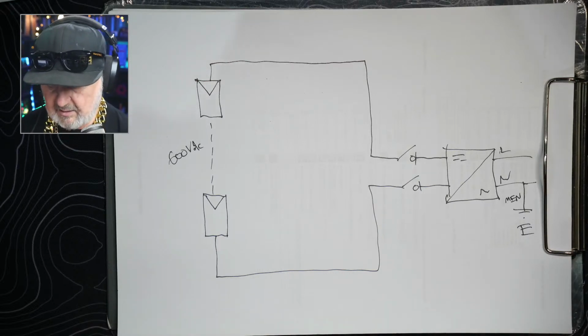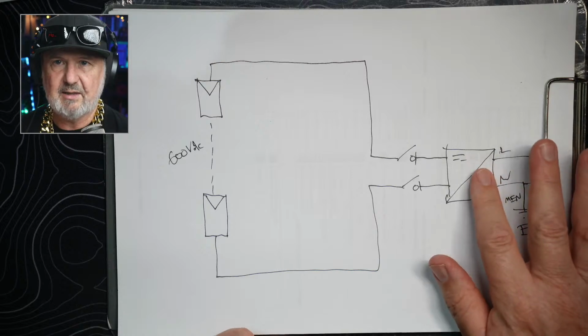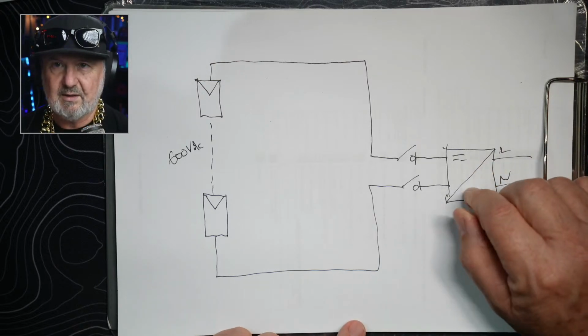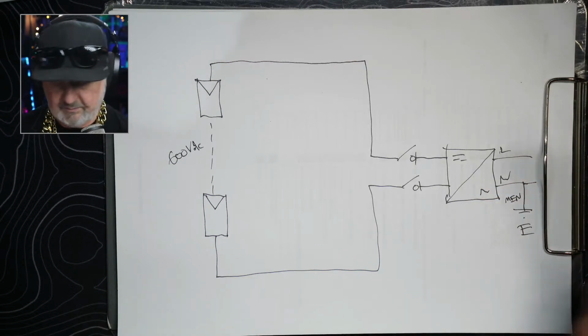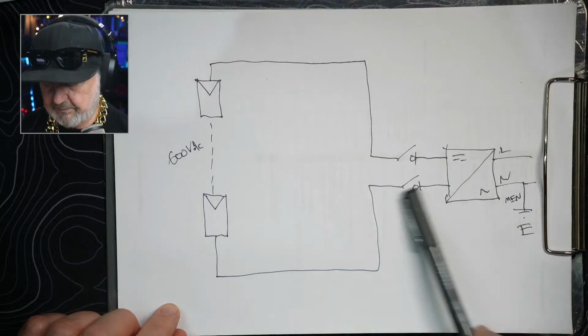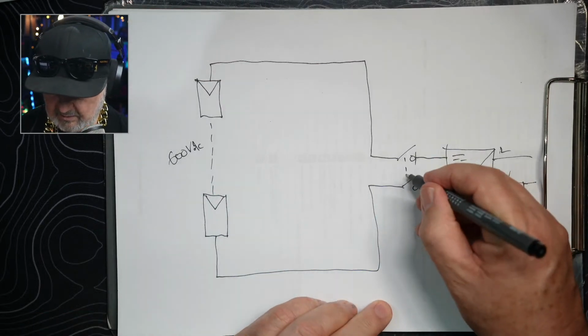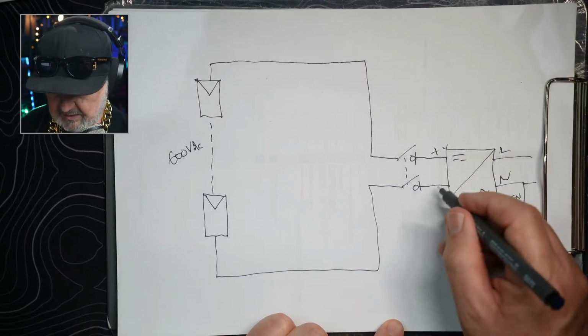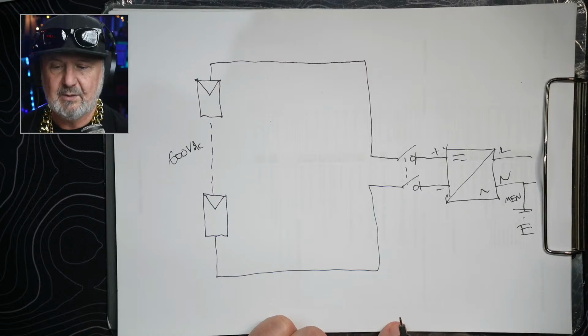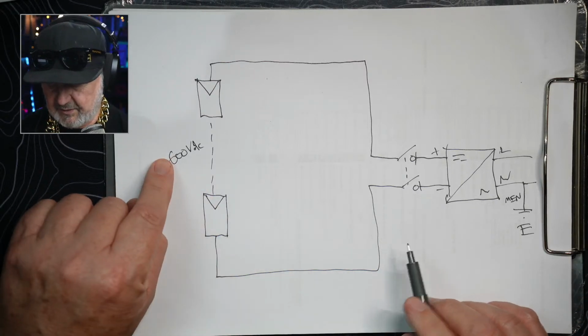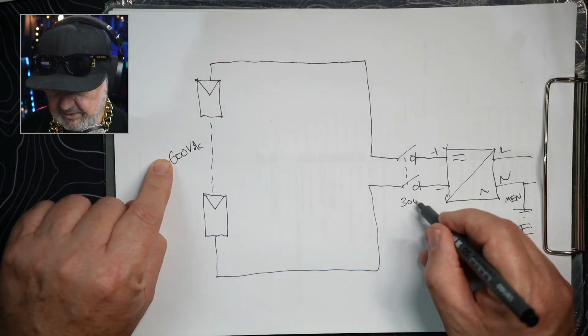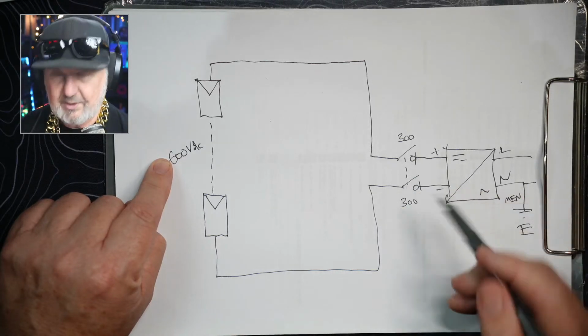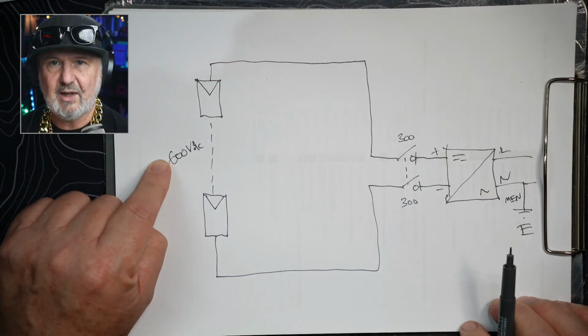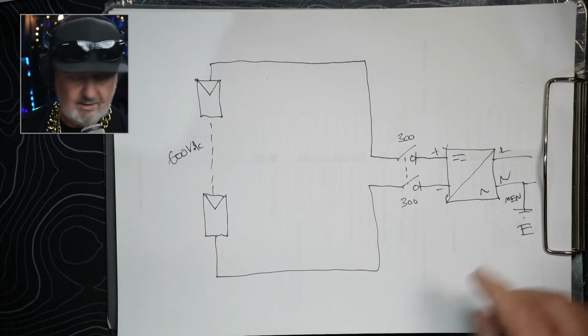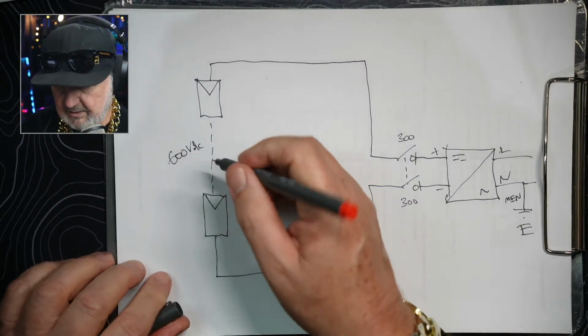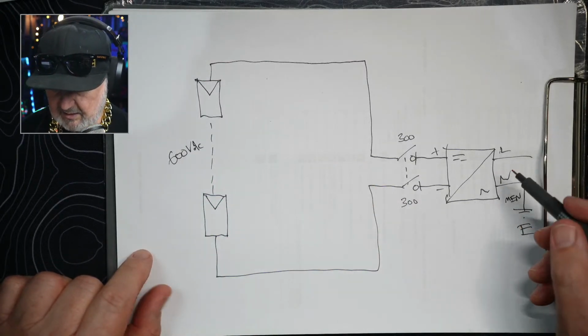Now, if this was a galvanically isolated PCE and it went faulty, short circuit internally, the fault current would be going basically around the circle, all around here. And that means when I switch off this ganged isolation device, both the positive and the negative poles are interrupted simultaneously, which actually means that the voltage of 600 volts is split evenly, 300 on this side and 300 on this side. So the switch doesn't actually have to do so much work because it's only breaking 300 volts at the fault current.